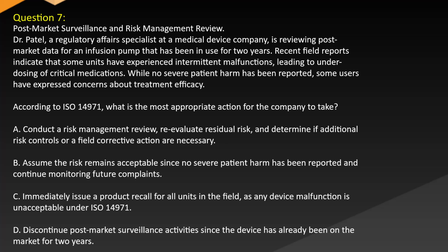A. Conduct a risk management review, re-evaluate residual risk, and determine if additional risk controls or a field corrective action are necessary. B. Assume the risk remains acceptable since no severe patient harm has been reported and continue monitoring future complaints. C. Immediately issue a product recall for all units in the field as any device malfunction is unacceptable under ISO 14971. D. Discontinue post-market surveillance activities since the device has already been on the market for 2 years.